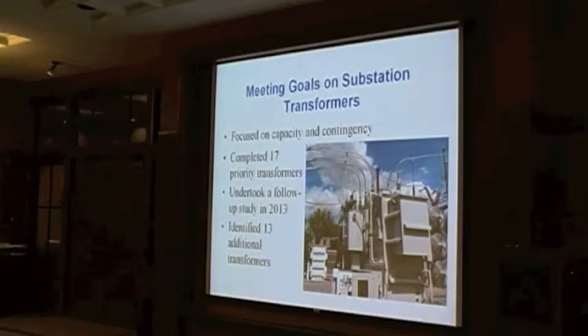The substation transformers take the power from the 69 kV system, reduce that, and place it on the local distribution system. This program was all focused on contingency, which is, in essence, the backup capacity in a station to help support other stations if need be, or other customers along the line.